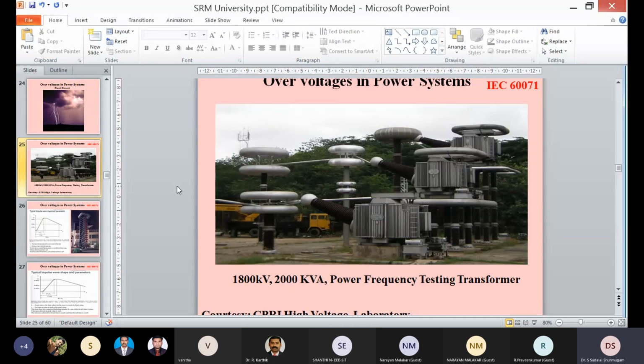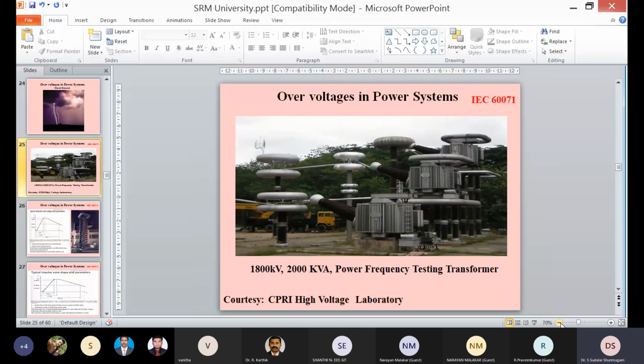How will this power frequency fault be created in actual laboratory conditions? We will have a power frequency testing transformer. I'll just reduce the size so that you can see that. What you are visualizing is a power frequency testing transformer, 1800 kV, 2000 kVA, a cascaded connection transformer.